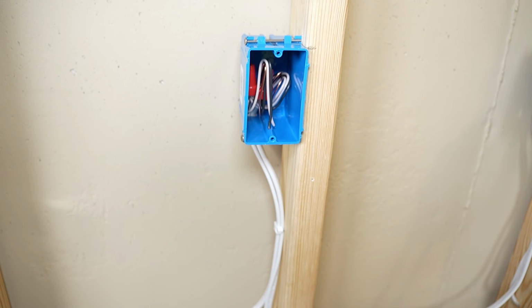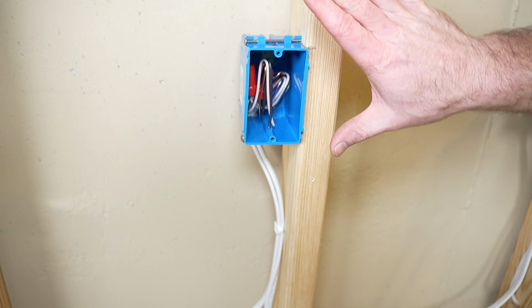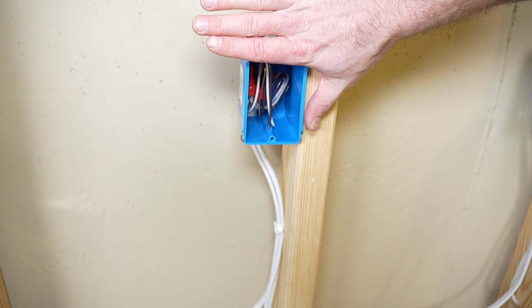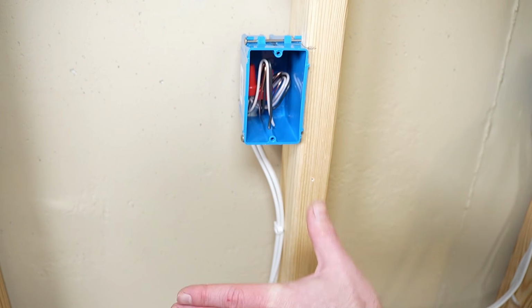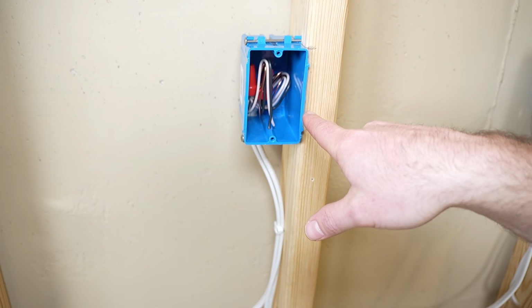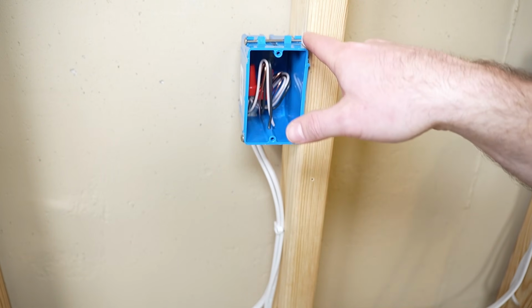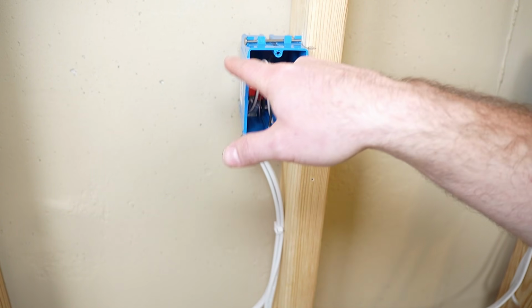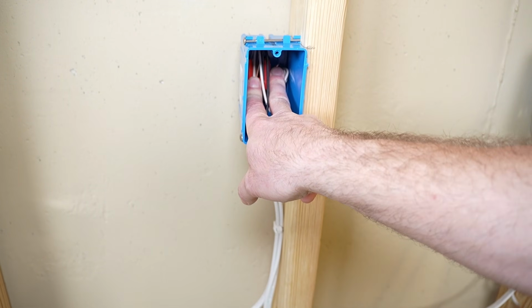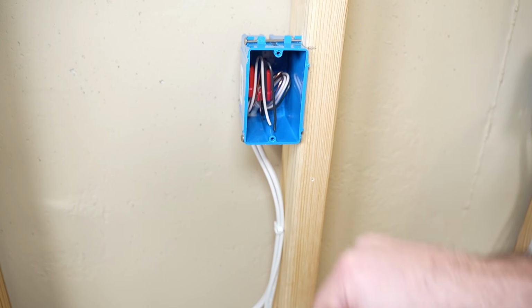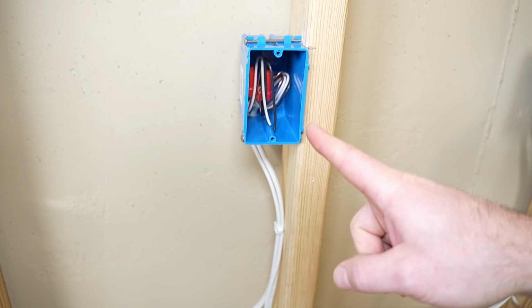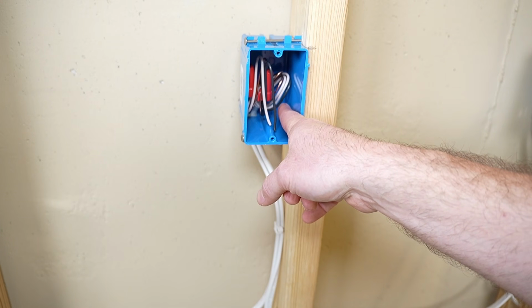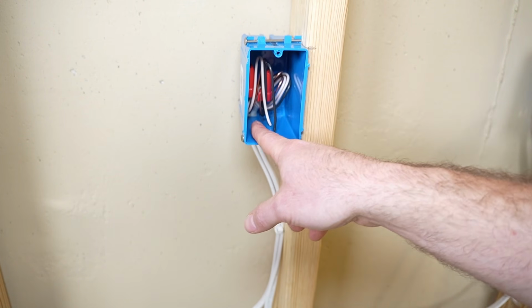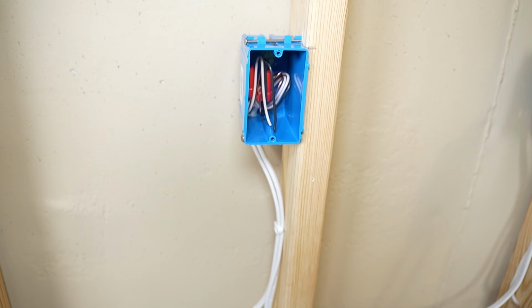So with our wires safely in the back of the box, when the sheetrocker comes to put the sheetrock on the wall, all they do is put up a big piece of sheetrock and then they come through with a rotozip later and cut out the box from the sheetrock. So it's very important to make sure your wires are as far in the back of the box as possible, because that rotozip blade has a tendency to be a little too deep and they will cut your wires as they cut out the sheetrock for your boxes.